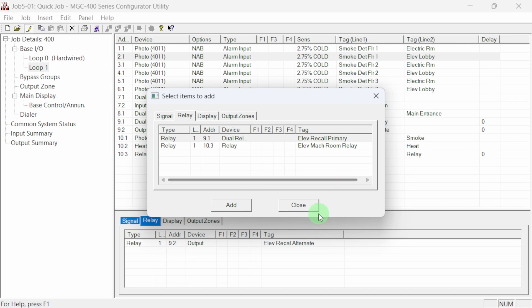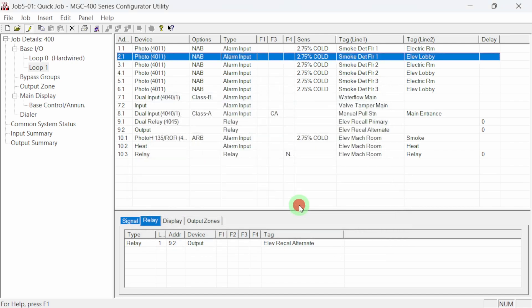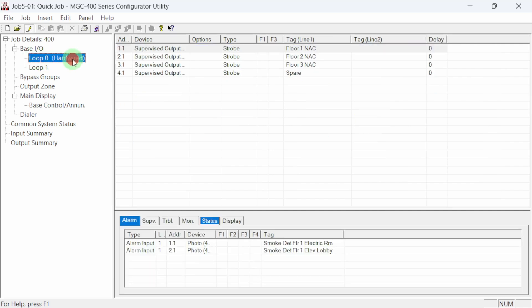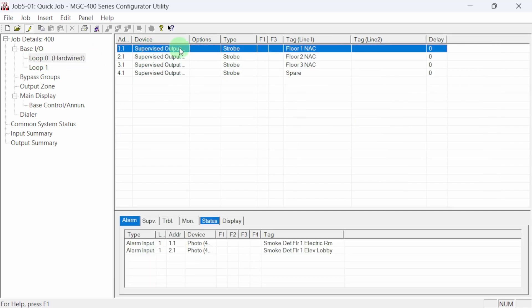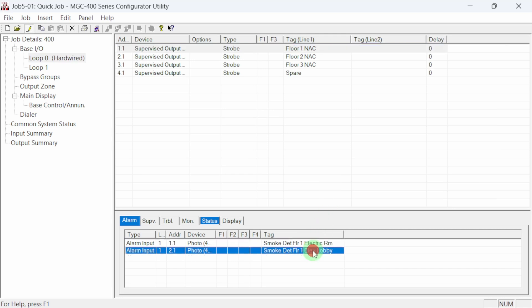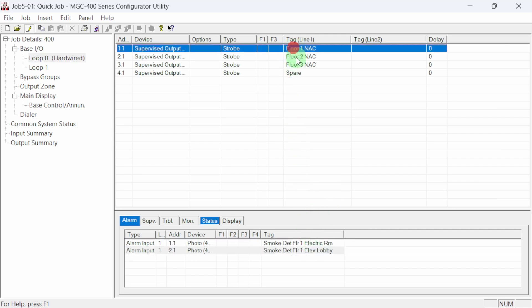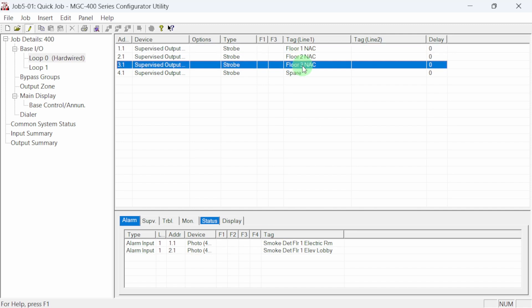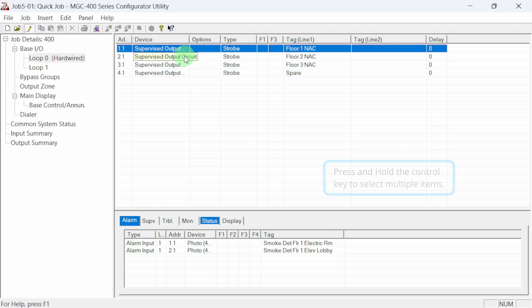Each of our alarm input devices needs to be correlated to the NAC circuits. We could follow the same process selecting and adding correlations to each input device. A quicker way is to directly correlate the NAC circuits to the alarm input devices. Navigate to loop zero where the NAC circuits are. When we highlight a NAC, the input circuits and devices that are correlated to it show in the details area. The two smoke detectors we previously correlated show here. Let's quickly add all of the alarm input devices to trigger all of the NAC circuits.